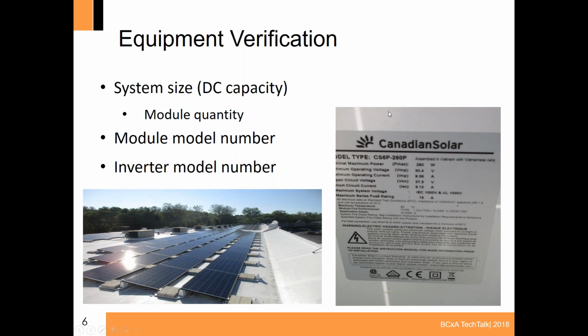So the nameplate on the right-hand side, you can see that each one will have a maximum power rating, or Pmax. That's typically the rating we go by when we talk about the system size. So in this case, it's 260 watts, and say if we have 100 solar panels or so, we would just multiply that together and get the final DC nameplate rating of the system. So it might be cumbersome to count hundreds of modules, but again, it's important to verify that the proper equipment was installed. Once we can get the count, get the nameplate information, then that's how we verify the system size.